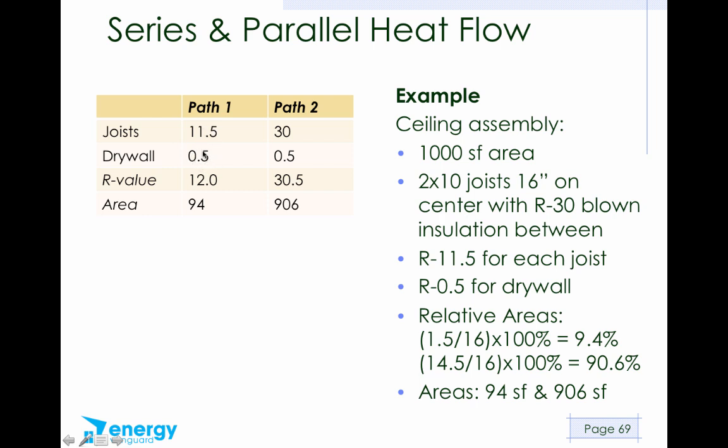That's the layers, the series heat flow. So the total R value is the sum of those, so it's 12.0. If it goes through the insulation, it encounters an R30 through the insulation, then 0.5 through the drywall. So the total would be 30.5. Here are our two areas. So these are the numbers that we need for the equation.